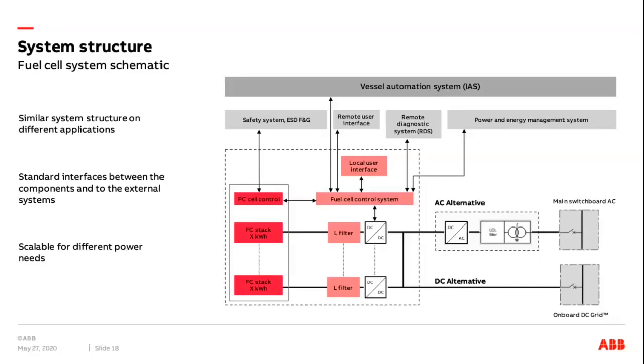Electrically, this is integrated through a DC-DC converter. As the voltage on the fuel cells varies with the load, we typically have a high voltage at low load, and as the load increases, the voltage drops. So we need a DC-DC converter to make the voltage stable. If you have an onboard DC grid system, this can be connected directly to the power grid on board the ship. If you have an AC system, however, you need to go through a DC to AC converter and a transformer, and then connect the fuel cell to the main switchboard, being a low voltage or medium voltage switchboard.